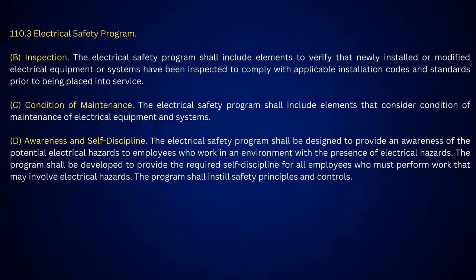Now, as I go through and look at this, I also tell you inspection. They tell you the electrical safety program shall include elements to verify, and listen to what it says, that newly installed or modified electrical equipment or systems have been inspected to comply with applicable installation codes and standards prior to being placed in service. That goes back to what I was saying. As an example, if I go look at 110.24(B) for my available fault current, and you start adding to the system and upgrading it, you've modified it at this point. That can change what the available fault current is there.